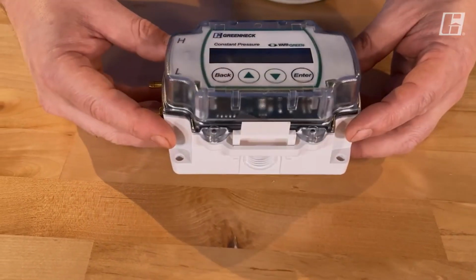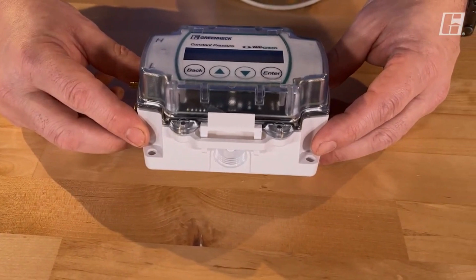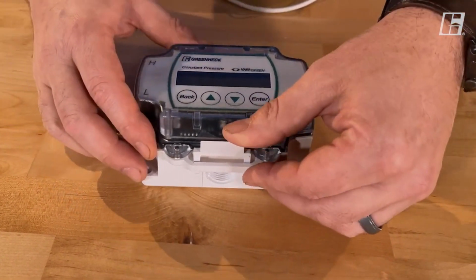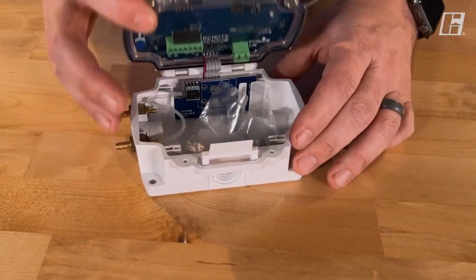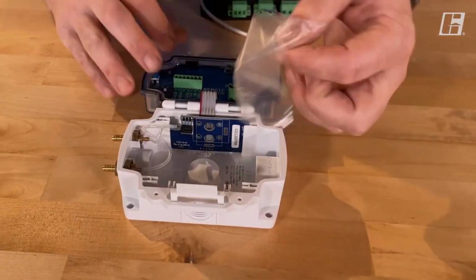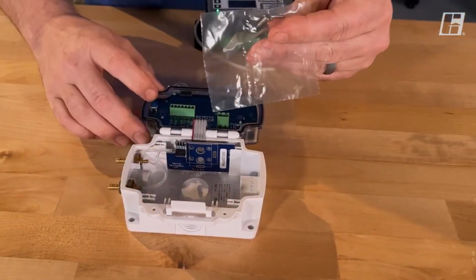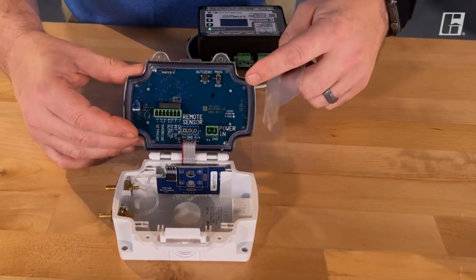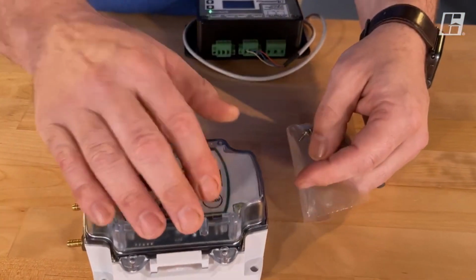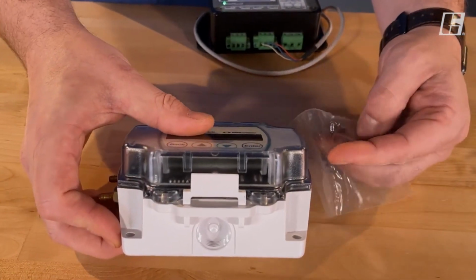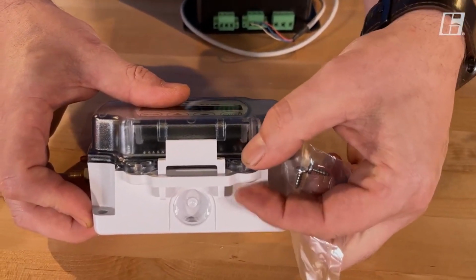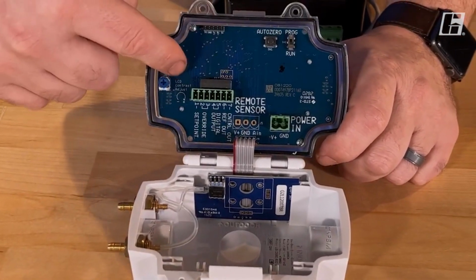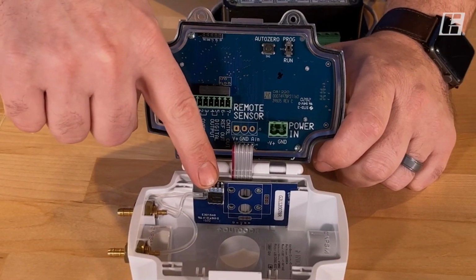Let's crack this open and kind of talk about what's all inside. First off, this control is in a NEMA 4 enclosure. To get inside of this enclosure, we just push down on our little lever here and we can flip this open. Inside, from the factory, you'll find 2 little screws. This is important because of the rubber gasket right here. To maintain that NEMA 4 rating, when this is all done and installed, these screws do need to be installed in these 2 points. Now inside here, we have our PID controller and we have our differential pressure transducer.